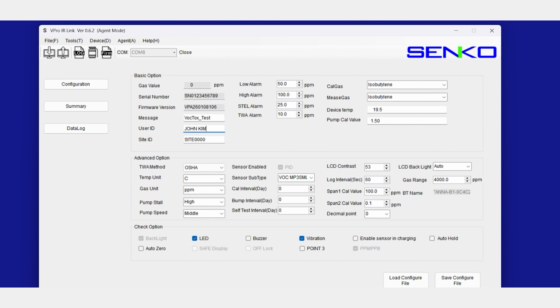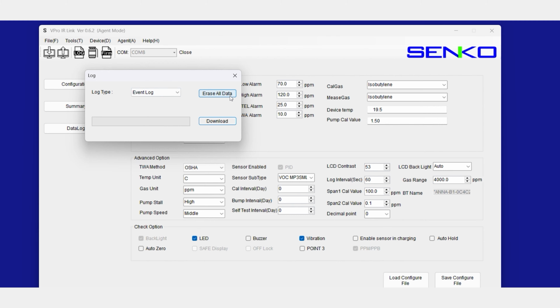Next, let's look at the main configuration and functions of the IR-Link software. After IR-Link connection, you can check device information and manage alarm values, gas types, and calibration settings. Also, you can load or modify settings stored on the device, and changes are saved to the device through the write function. Event logs, calibration history, and measurement data can be downloaded to the PC or deleted as needed, enabling systematic management of device history and inspection records.